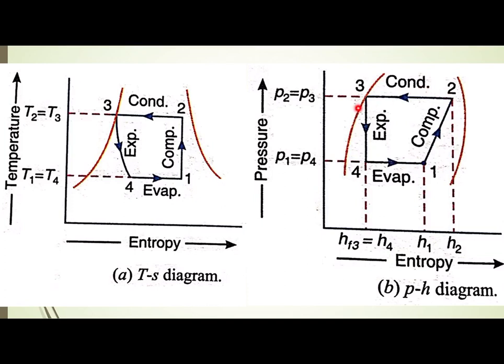All other processes are in the same manner as compared to the previous system. Process 1 to 2 is isentropic compression. Process 2 to 3 is isobaric heat rejection. Process 3 to 4 is isenthalpic expansion. And process 4 to 1 is isobaric heat absorption.